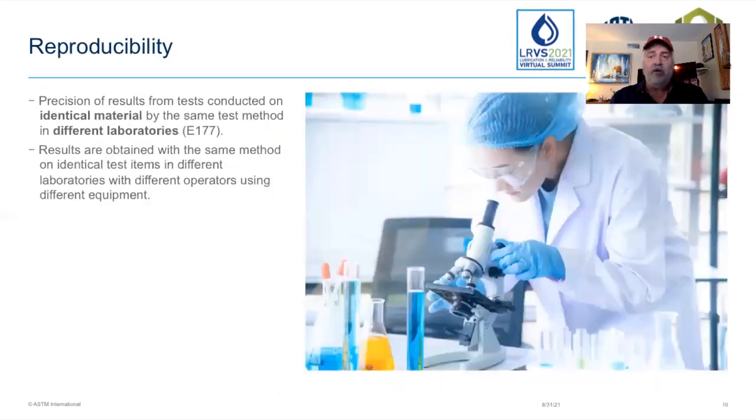This becomes a little more complicated when we introduce multiple labs into it. So one of the problems with this would be that if your particular service provider provides a measurement that does not have good reproducibility, then when others talk about that machine or that ppm iron or that ppm copper, whatever it might be, their data or their starting point, their bias could be from a different quadrant altogether. And so the data really doesn't talk well and is really disassociated.